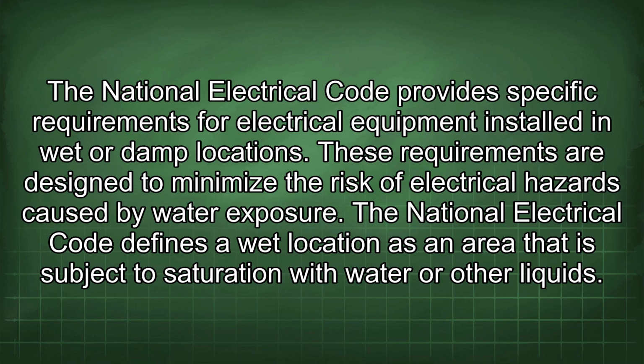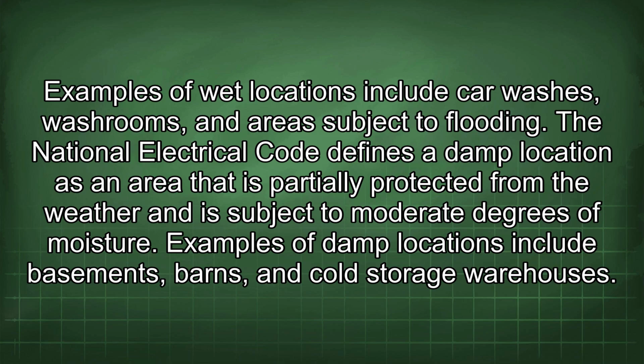The National Electrical Code defines a wet location as an area that is subject to saturation with water or other liquids. Examples of wet locations include car washes, washrooms, and areas subject to flooding. The National Electrical Code defines a damp location as an area that is partially protected from the weather and is subject to moderate degrees of moisture. Examples of damp locations include basements, barns, and cold storage warehouses.